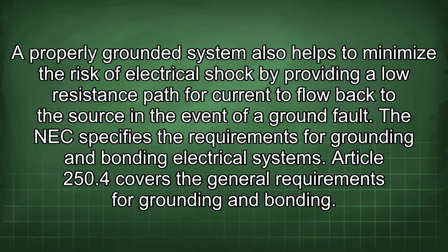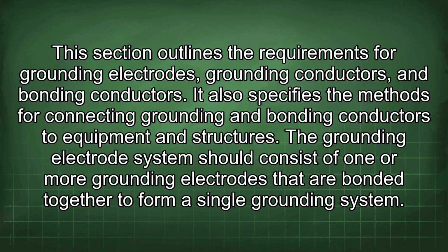The NEC specifies the requirements for grounding and bonding electrical systems. Article 250.4 covers the general requirements for grounding and bonding. This section outlines the requirements for grounding electrodes, grounding conductors, and bonding conductors. It also specifies the methods for connecting grounding and bonding conductors to equipment and structures.